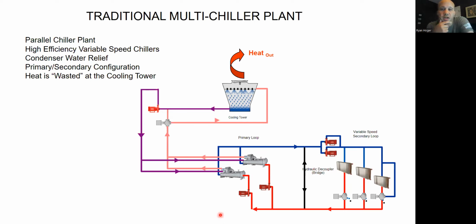It's not super common to have just 1 chiller, because then if something goes wrong and you've got to fix the machine, you've got to work on it for a day or 2, you have no cooling in the building, right? If you have 2 chillers, you have some level of redundancy. If one chiller's down, the other chiller can cool the building. And if it happens to be the hottest day of the year, at least the other chiller can half cool the building. All right. So that's much more common.